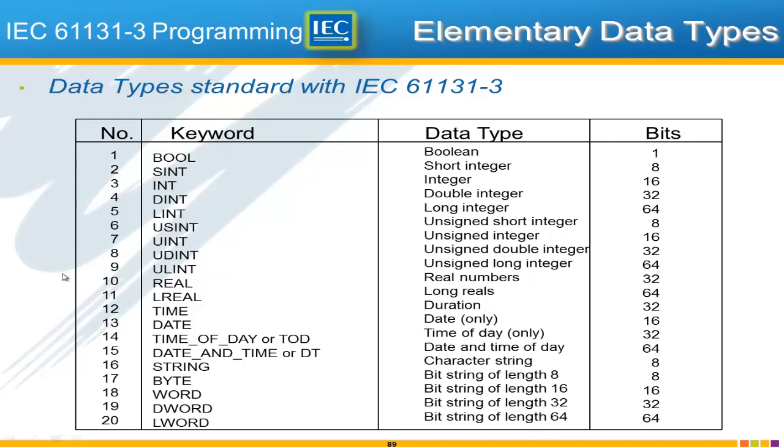And while this looks like a long list, in our experience at Yaskawa, there are a few of the data types that seem to appear and are used more often than others. So I've indicated those here. Bool for Boolean, you have a bit, 1 or 0, true or false. Integers for negative and positive counting variables. Unsigned integer, where you have just the positive values. The real, and probably more common, the LReal, meaning a floating point; a decimal point is implied and in fact required in those. You have time for the timers, and there's a special format for using the data in time.